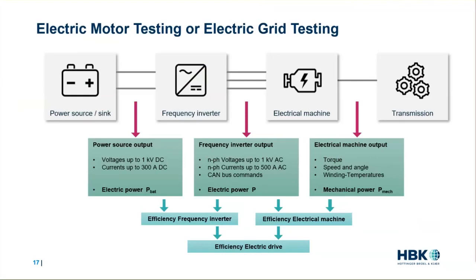So in this example, you'll often need to measure at the output of the power source or battery, as you see on the left. In fact, voltages up to 1,000 volts DC would be measured, currents up to 300 amps DC, and then at the output of a frequency inverter in the middle, you'll need to measure n number of phases of voltages up to maybe 1,000 volts AC, and n phases of current, maybe up to 500 amps AC. Now, in this application, you might also measure torque, speed, and position, so that you can calculate the mechanical power in addition to calculating the electrical power at the input and output of the inverter, which enables you to ultimately calculate the efficiency of the entire system or electric drive, or in reverse, the efficiency of the generator. Now, to do so, this requires high accuracy measurements.